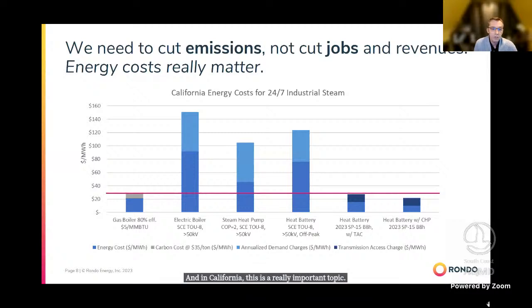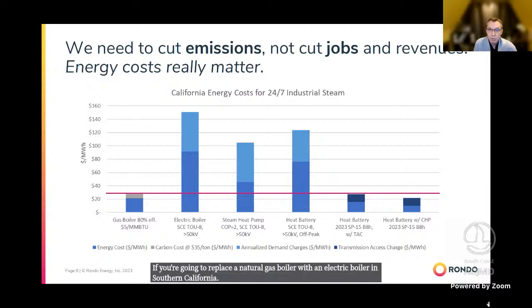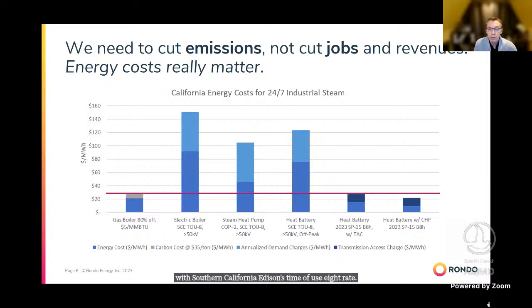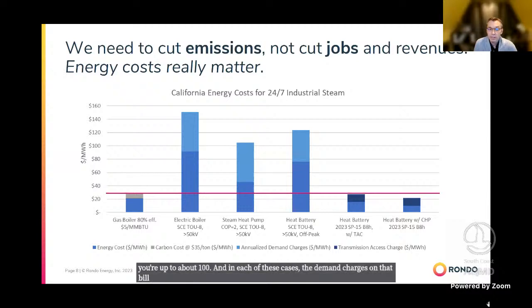So on the left, the first bar is what is the cost of steam today with natural gas? And this is just the fuel cost. So that's $5 a million BTU natural gas. It's a little bit cheaper than that today. And then the little gray line there is a $35 a ton CO2 price. If you're going to replace a natural gas boiler with an electric boiler in Southern California, with Southern California Edison's time of use 8 rate, an electric boiler is going to deliver steam, just the electricity costs, north of 150. If you're going to do it with a heat pump that has a COP of 2 on that same tariff, you're up to about 100. And in each of these cases, the demand charges on that bill are nearly half of it.